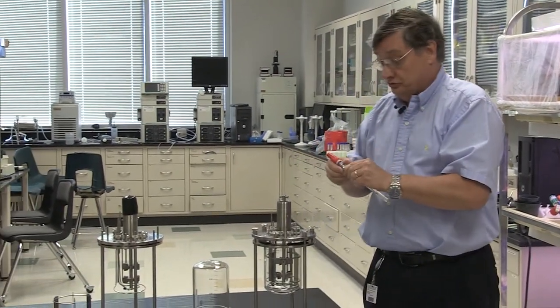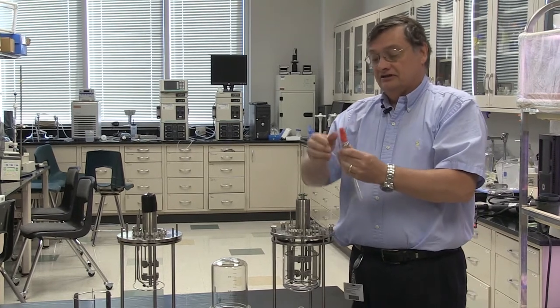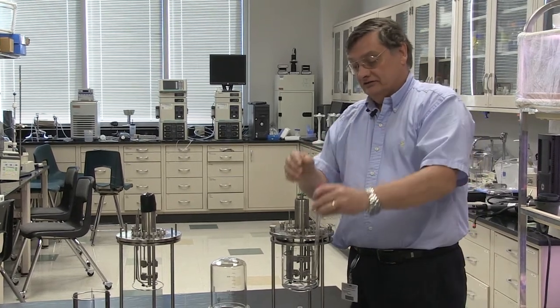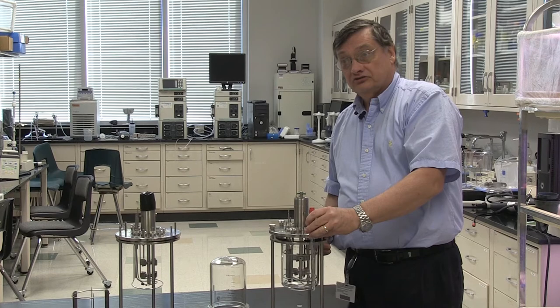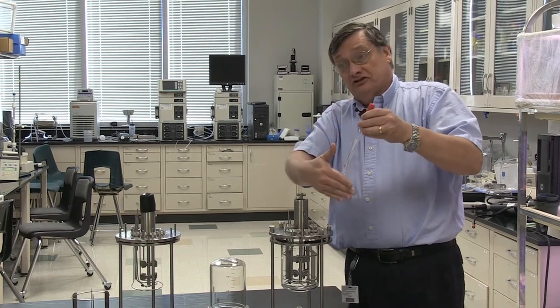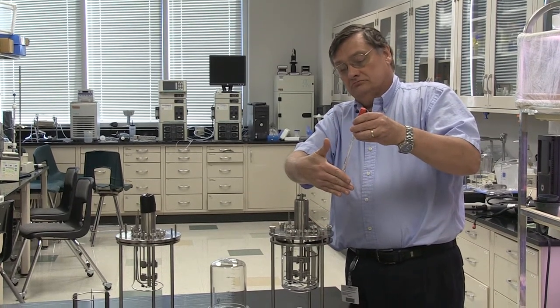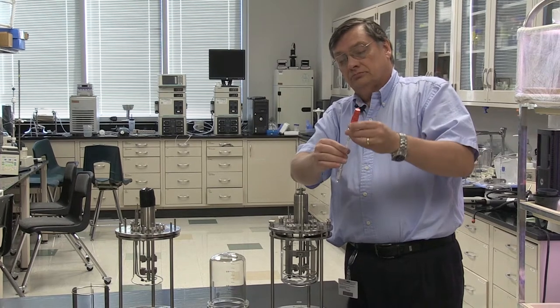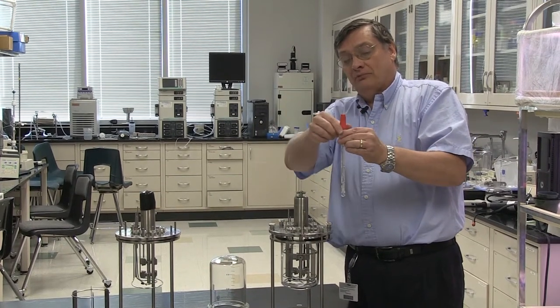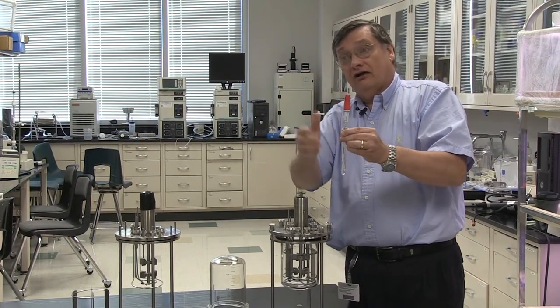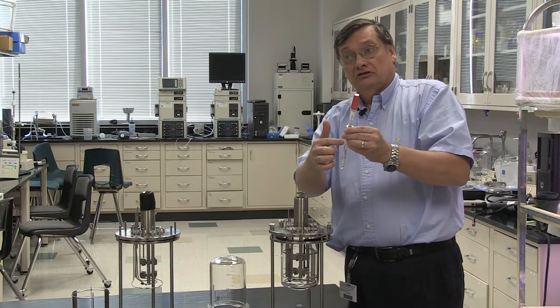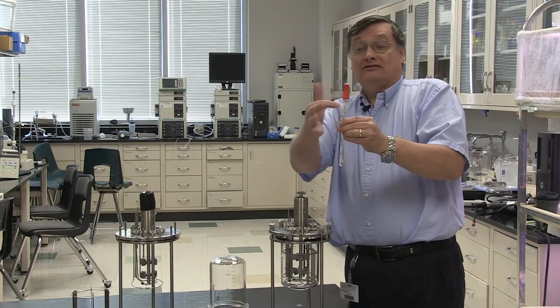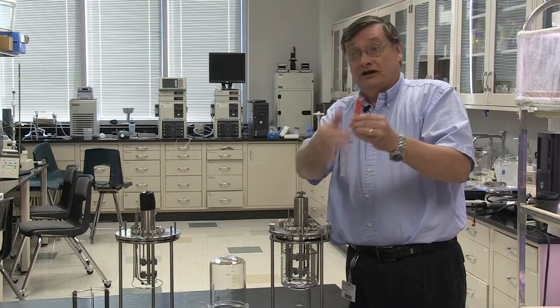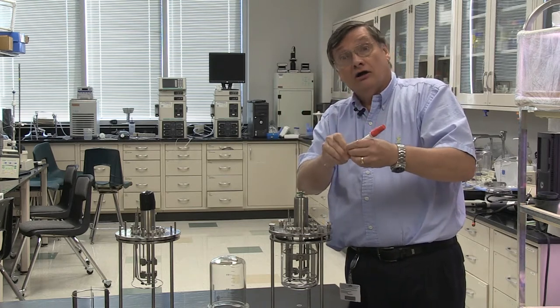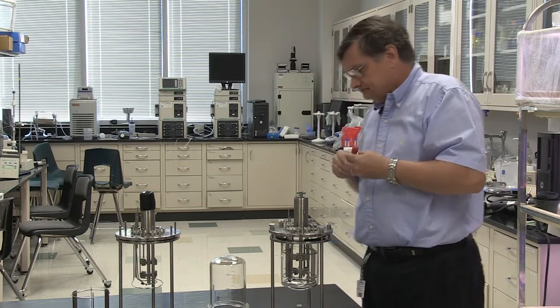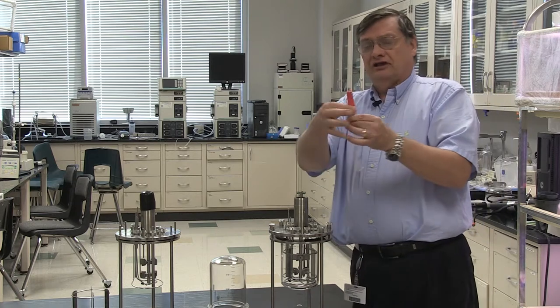What I prefer to do as it's being autoclaved is autoclave it in the completely down position. That sterilizes the entire probe. Then when you're operating it, if you want to pull it out a bit, then you can. But if you autoclaved it and left this exposed and push it down, you could be introducing organisms into the vessel. So that's a multi-piece fitting.